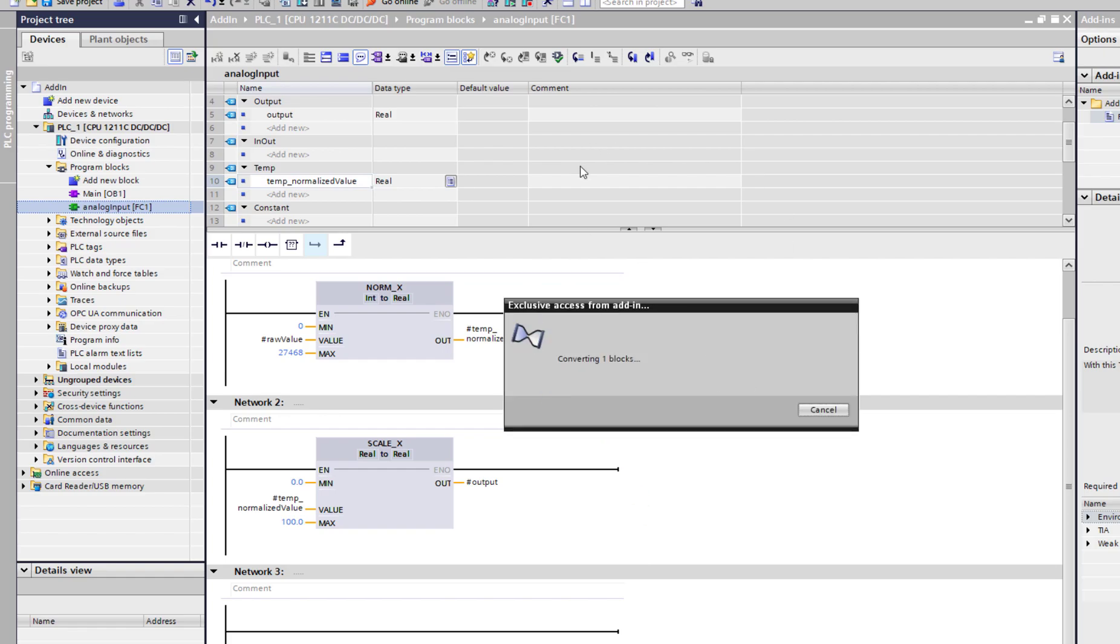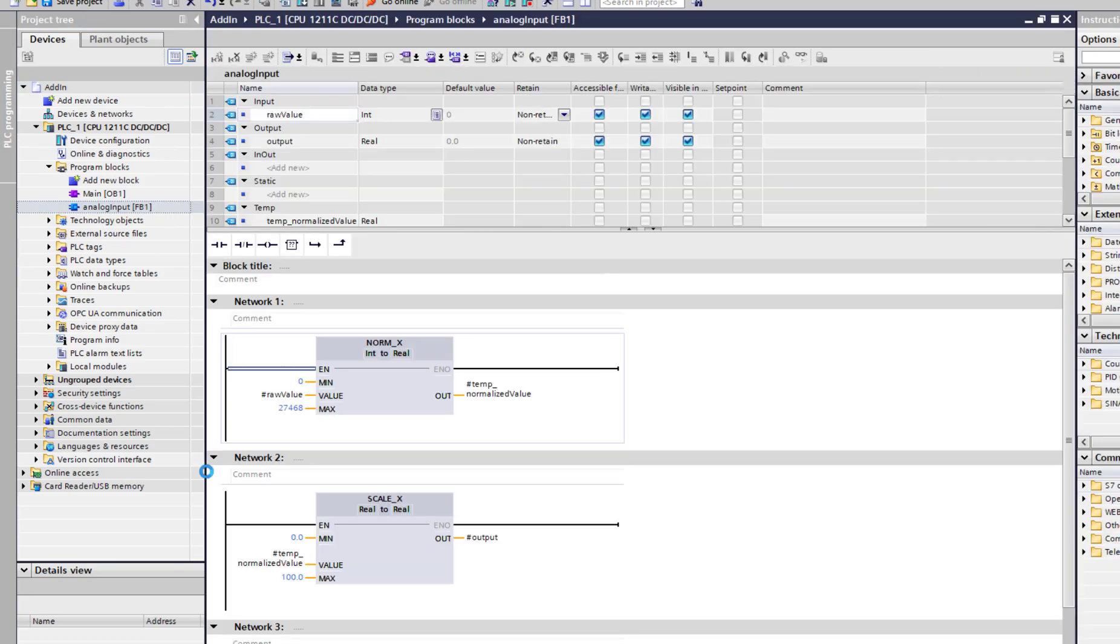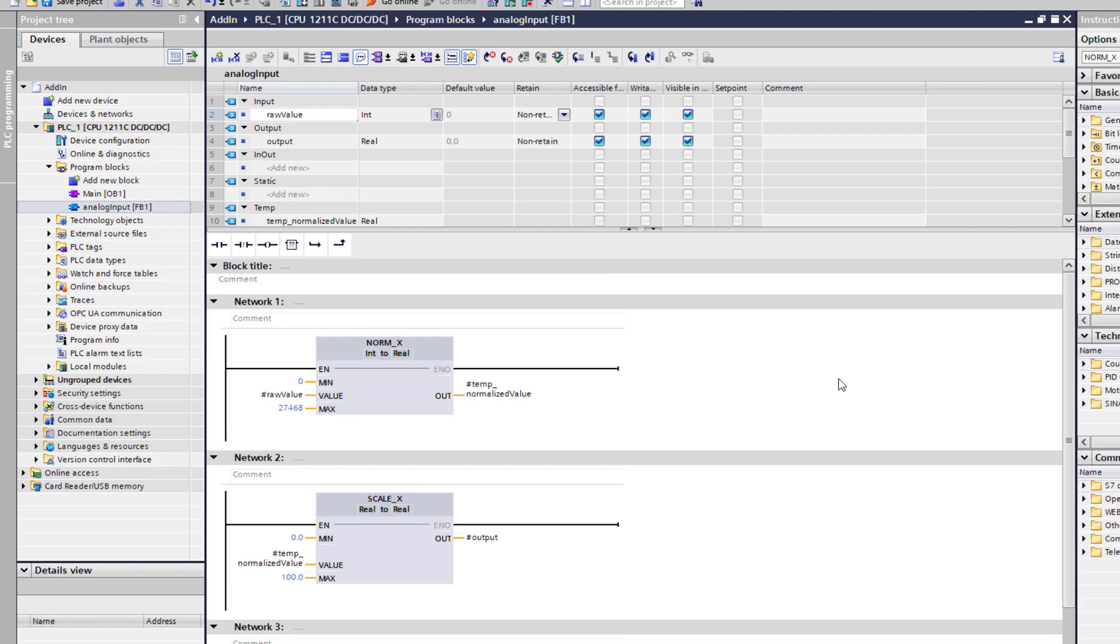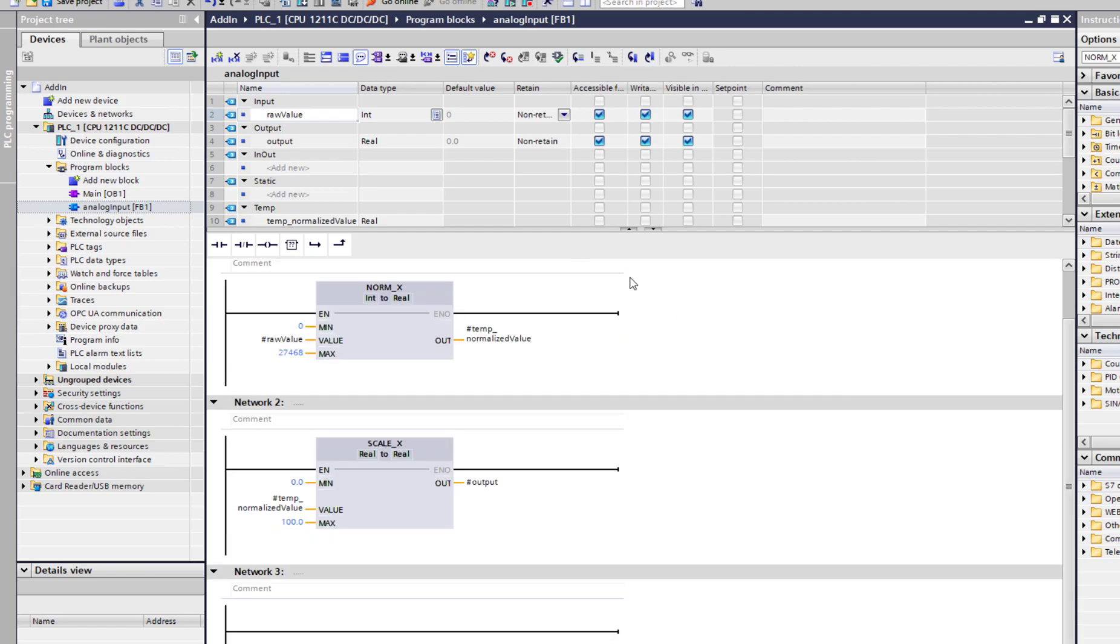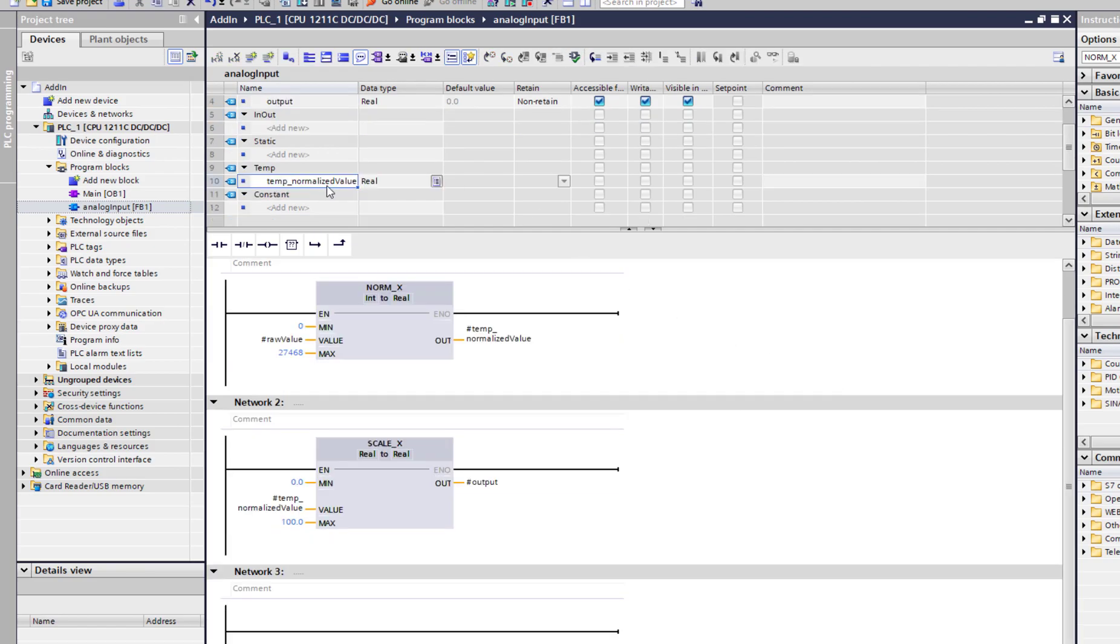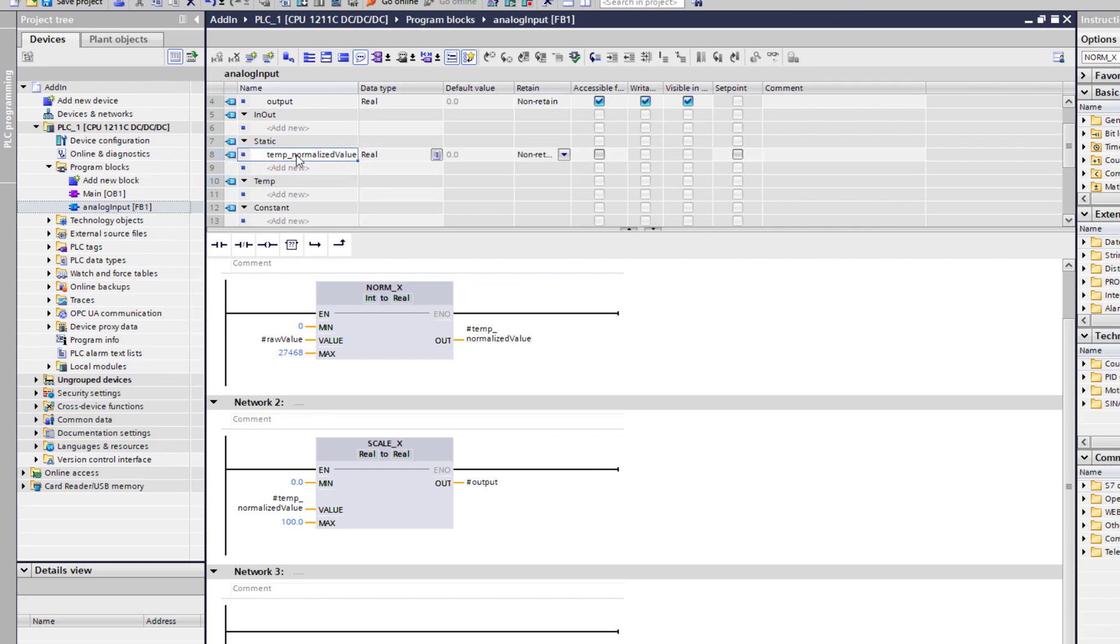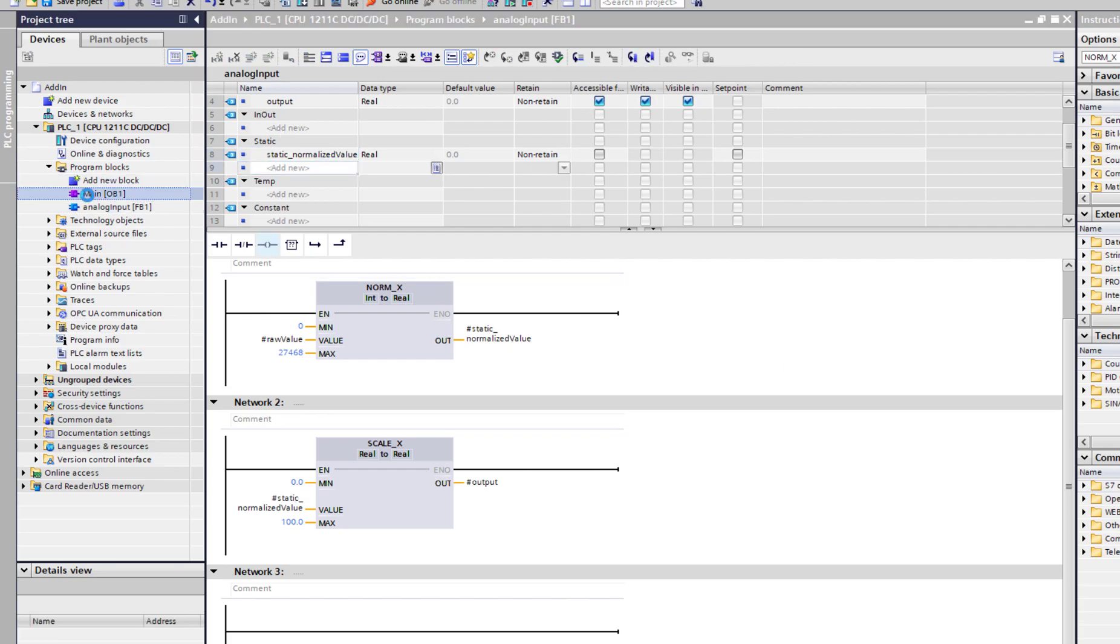So what it's doing in the background, it's actually using Openness to export this block in XML format and then re-import it back as a function block. So there you go. We now moved it. If I was interested in this being a static, I can just move it, change the name. There you go. Our FC is now an FB.